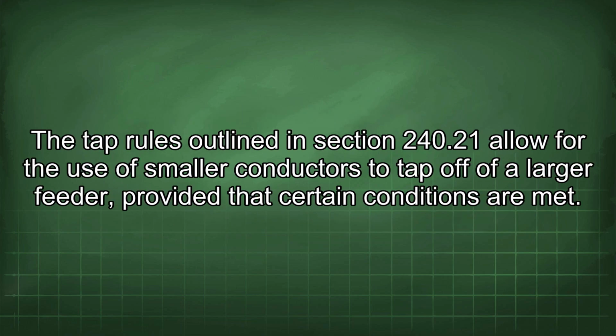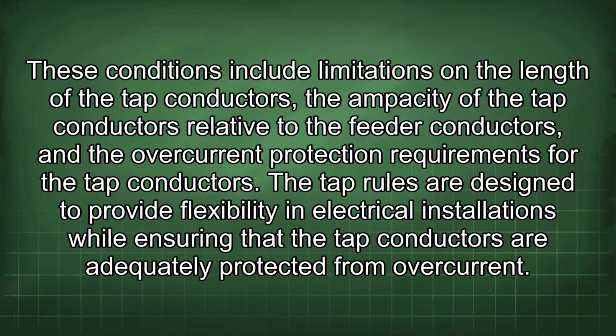The tap rules outlined in Section 240.21 allow for the use of smaller conductors to tap off of a larger feeder, provided that certain conditions are met. These conditions include limitations on the length of the tap conductors, the ampacity of the tap conductors relative to the feeder conductors, and the overcurrent protection requirements for the tap conductors.